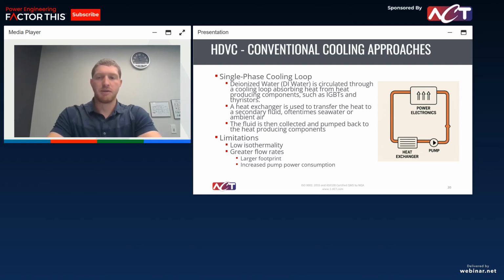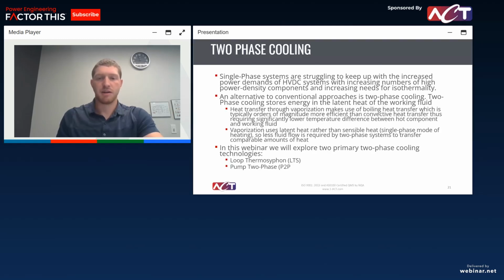Especially when you get into higher powers, you're going to need to be pumping your fluid a lot at greater flow rates as opposed to two-phase solutions, because that lower heat conductivity requires a greater pump or greater fans, just a larger system footprint, larger power consumption. So you're not going to be as efficient there, and that cost per kilowatt, as Knut was talking about, is going to be much higher.